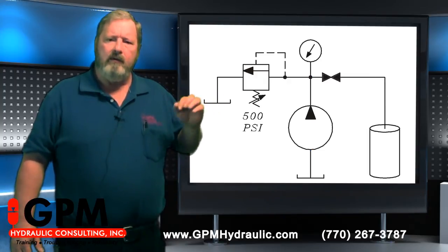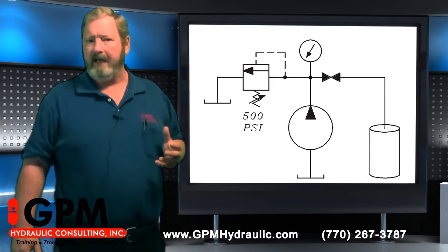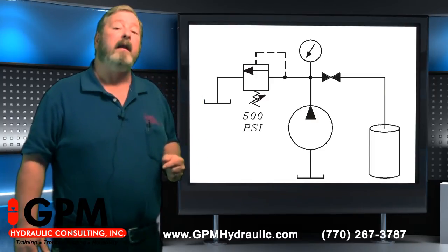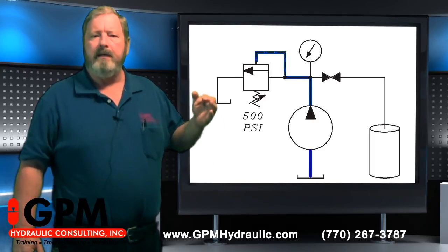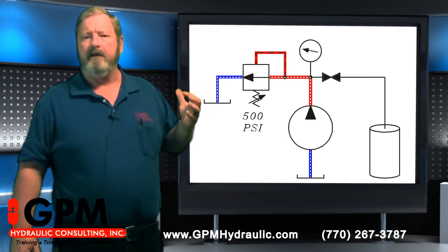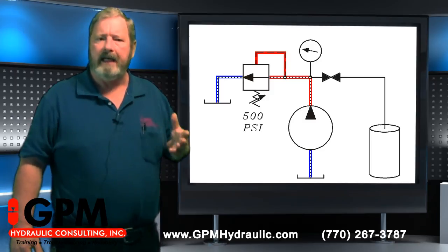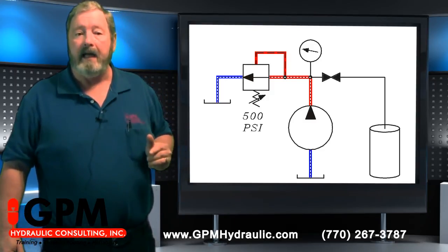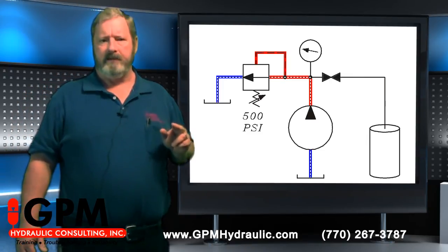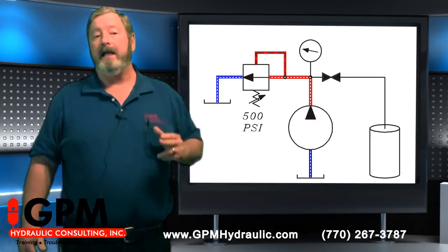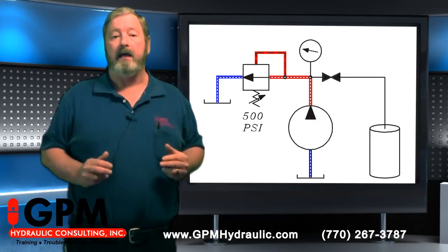Now if I close the hand valve, I've blocked off my no-resistance flow path. There is no flow path except through the relief valve. What's going to happen now? When I turn the pump on, pressure is going to build. Once it gets to 500 PSI, it will go through the relief valve and back to tank. What does my gauge read now? 500 PSI. Like I said, what you're reading on a gauge is not the pressure the pump is putting out — what you're reading on the gauge is how much resistance is currently being overcome in the hydraulic system.